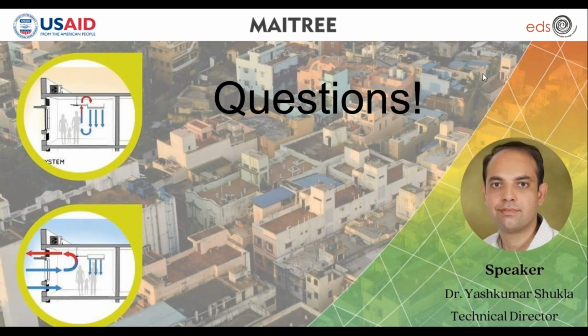the infiltration exfiltration. So I would still recommend minimizing the infiltration exfiltration for all buildings, including natural ventilation buildings, so that you have better control of the air circulation. The importance of that is less compared to the completely sealed air conditioned building, where the infiltration leads to increased penalty in energy consumption. For natural ventilation, you are just going to have uneven distribution, uneven pressure differential to be able to clearly understand how your air path movement will be through natural ventilation.